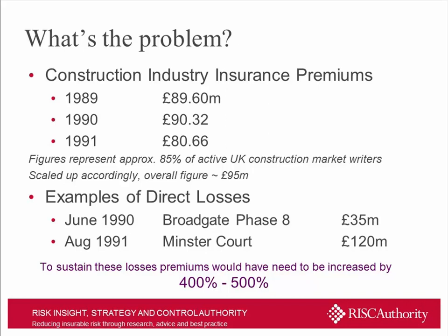The atrium was lined with scaffolding. For some strange reason, they'd been using polystyrene blocks cased in cardboard to support the scaffolding. I'm not quite sure how that arrangement functions, but it was these sorts of materials that were ignited, and the fire spread up through the atrium and did a huge amount of damage. It blew the top off the atrium eventually. The figures you see bandied about for the losses as a result of the fire are in the region of 120 million. I've seen figures which suggest it was about 105, with consequential losses beyond that of an additional 60 million pounds, so quite significant.